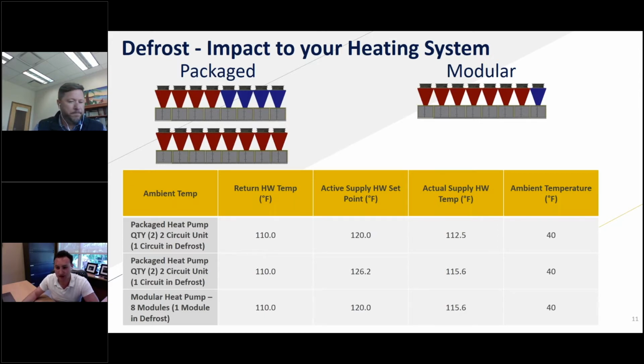Okay, great. Then next question is, how do you tell when defrost cycle can change over? So if you're talking within the machine, that gets into strategy on defrost, and there's multiple ways of doing that. Regardless, a manufacturer has simpler ways of doing it, which would be simply a time interval, right? Regardless of what's happening with your machine, it simply will look at, and if you want to make it a little more complicated, whether it's below a certain ambient. And anytime I'm below a certain ambient, I'm going to go into defrost every 15 minutes, right? So there are some of those strategies that exist from manufacturers.